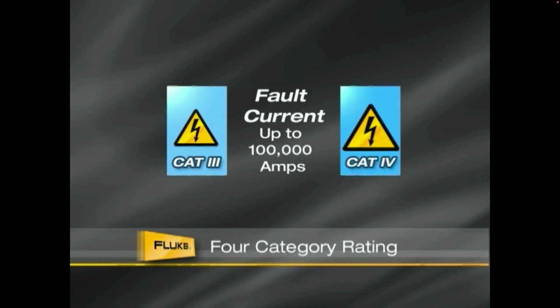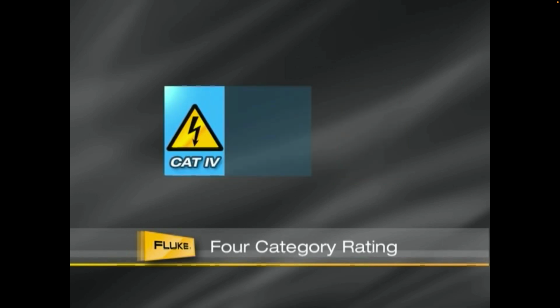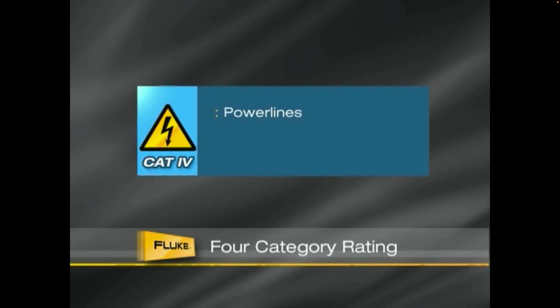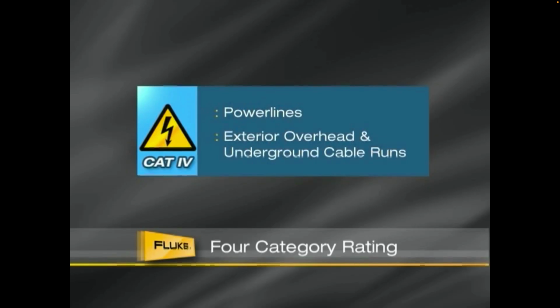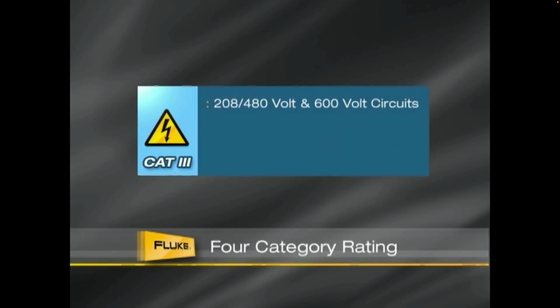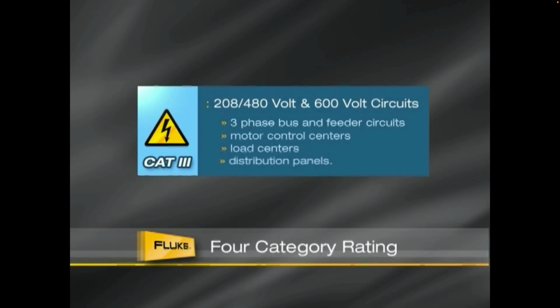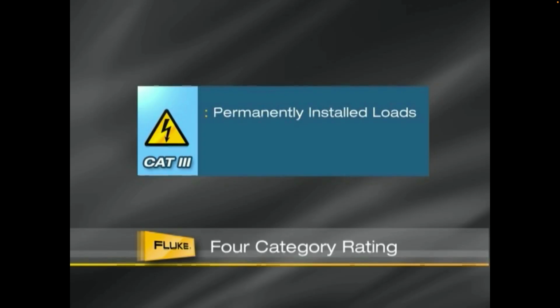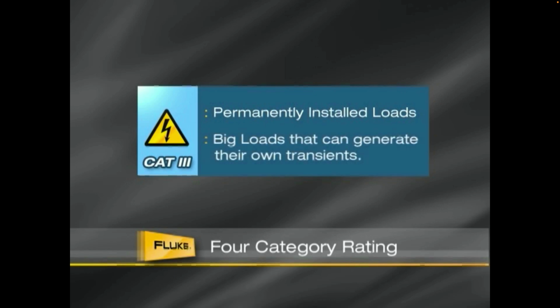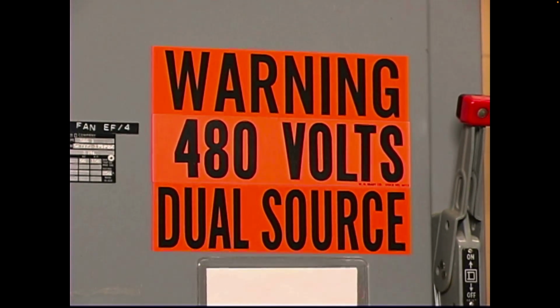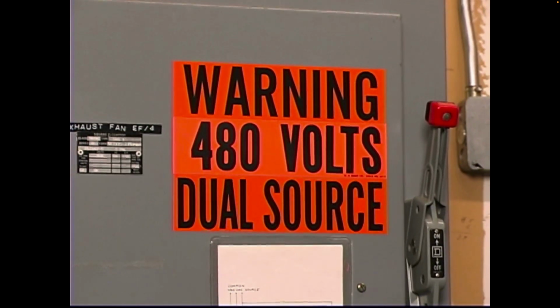The available fault current in these high-energy circuits can reach as much as 100,000 amps. CAT 4 refers to power lines at the utility connection, but it also includes exterior overhead and underground cable runs, since both may be affected by lightning. CAT 3 covers distribution level wiring. This includes 480 or 600 volt circuits, such as three-phase bus and feeder circuits, motor control centers, load centers, and distribution panels. Permanently installed loads are also CAT 3. CAT 3 also includes big loads that can generate their own transients and are now more common than many people realize. The trend to using higher voltage levels in modern buildings has changed the picture and increased the potential hazards.